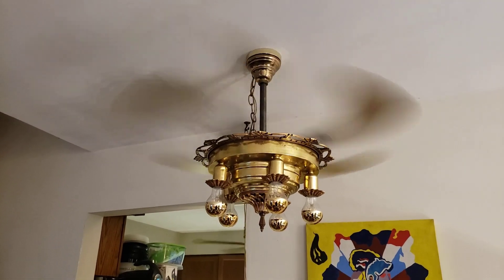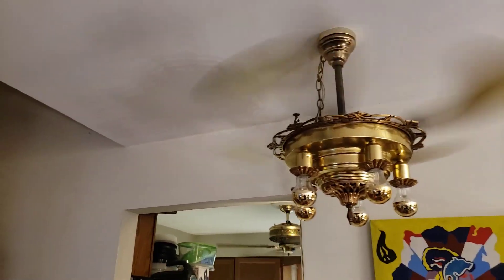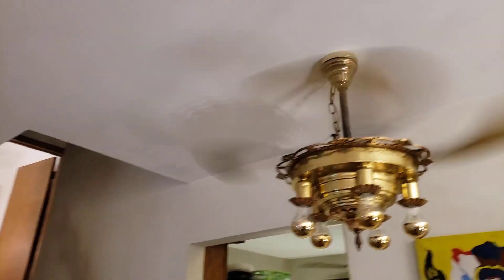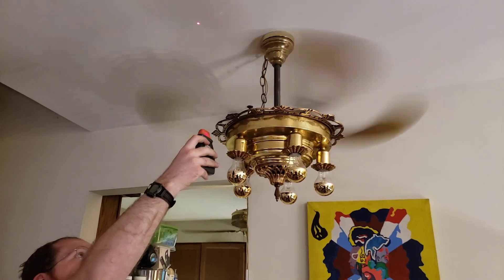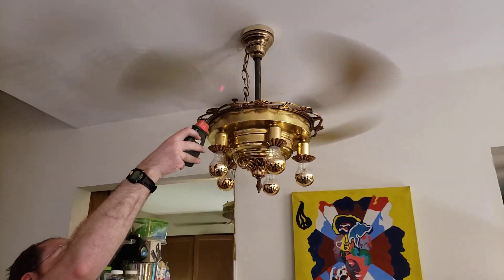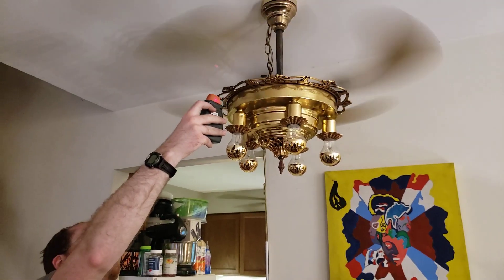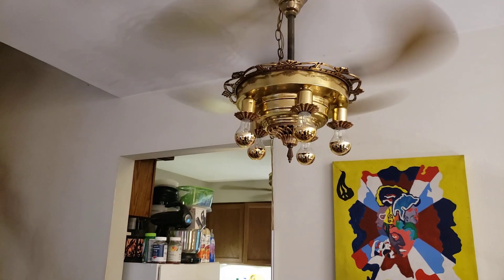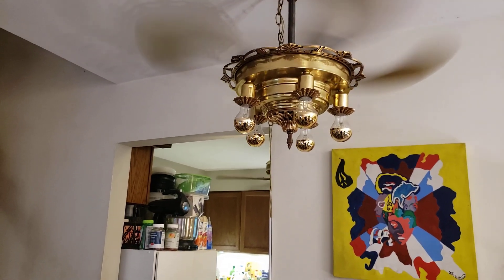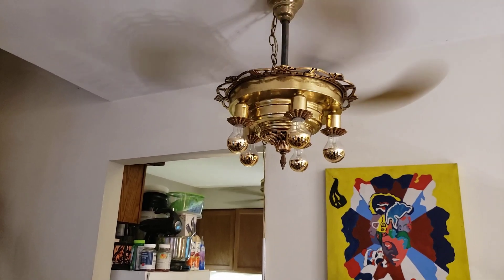So that one is about 4,000 CFM, which is pretty good for a 36-inch fan. Yeah, it's definitely pretty good. Should we do RPM too? Sure, it should be flying — yeah, and it's gonna be really clean. It should be. Yeah, it's about 387. That seems about right. That's right.